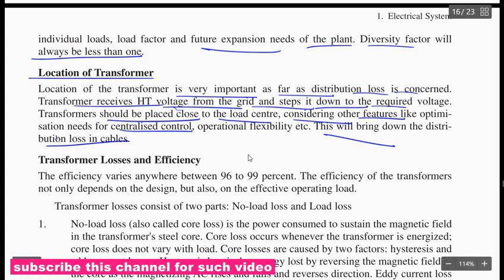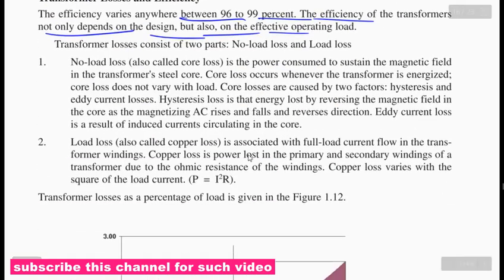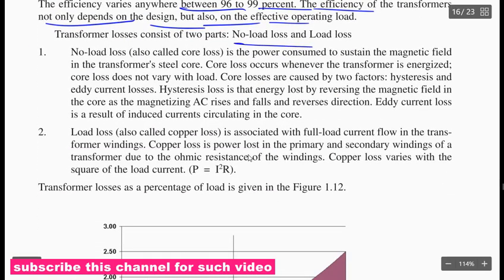Transformer losses and efficiency. The efficiency varies anywhere between 96 to 99%. The efficiency of a transformer depends not only on the design but also on the effective operating load. Transformer losses consist of two parts: no load losses and load losses. No load losses, also called core losses, are the power consumed to sustain the magnetic field in the transformer steel core. Core losses occur whenever the transformer is energized. Core losses do not vary with load.